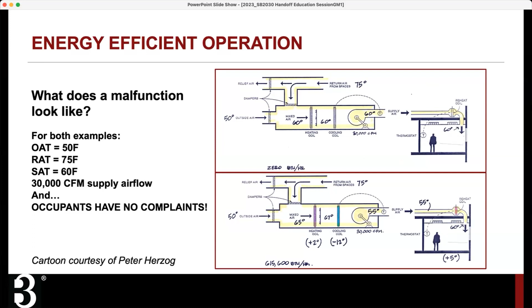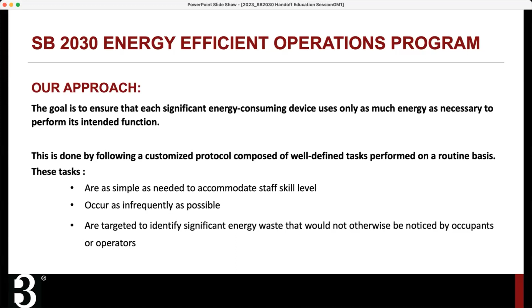In our SB 2030 Energy Efficient Operations program, we approach this by creating a customized protocol composed of well-defined tasks that are performed on a routine basis. And a few attributes of these tasks: they're as simple as needed to accommodate the skill level. There might be some cases where you have a very sophisticated building staff. They can look at trend logs, look at things over time, but you can also train somebody to go in and just look at this at a moment in time and determine right now, is this functioning correctly or not? The tasks occur as infrequently as possible, and that's to minimize the load on operations staff that are already overburdened and very busy people. And they're targeted to identify significant energy waste, so they're only looking at the biggest energy consumers, and that waste would not otherwise be noticed by occupants or operators unless they went to go and look for it, like that previous example.